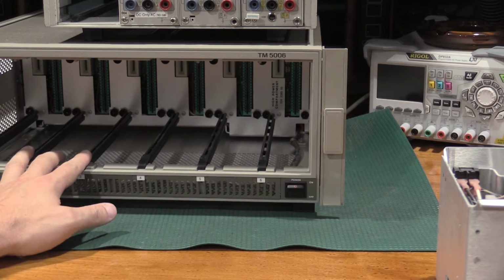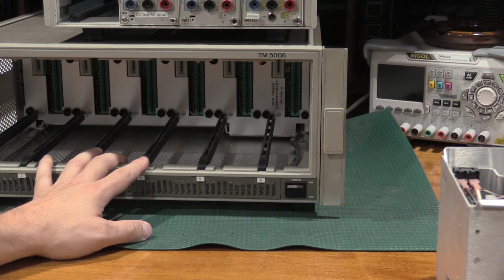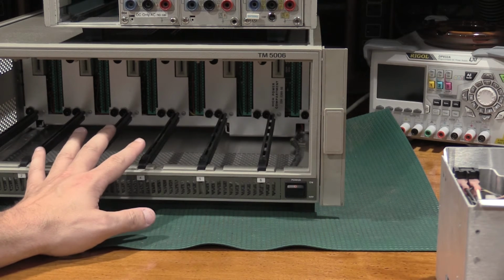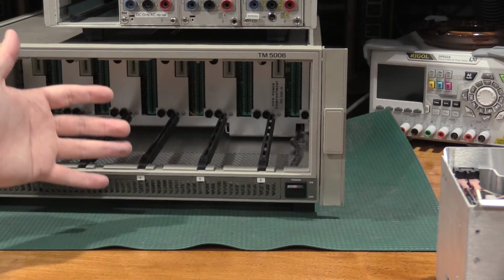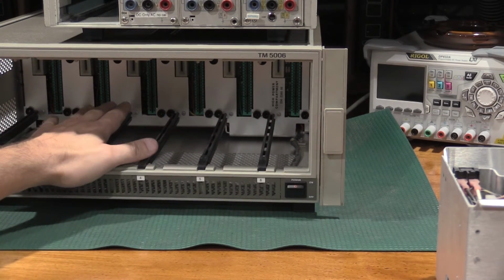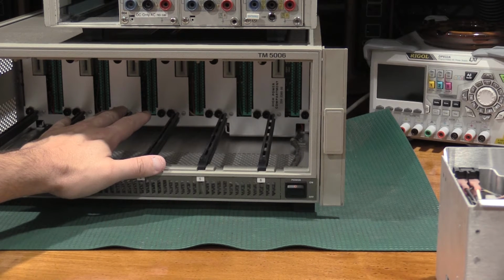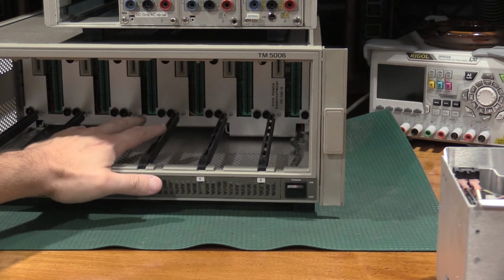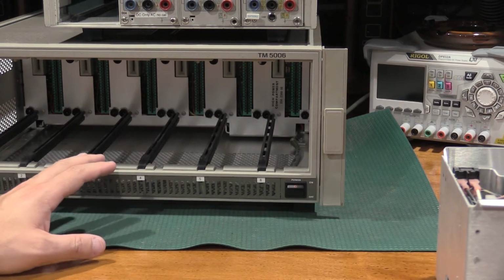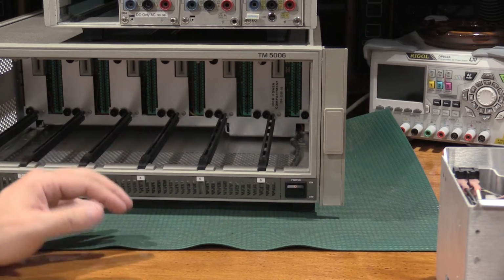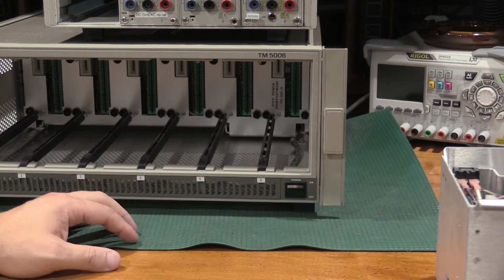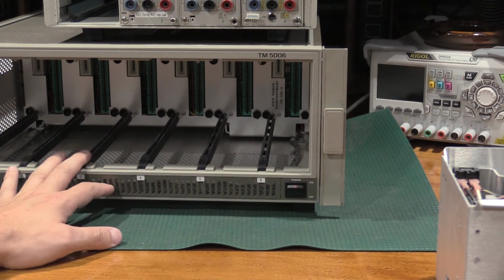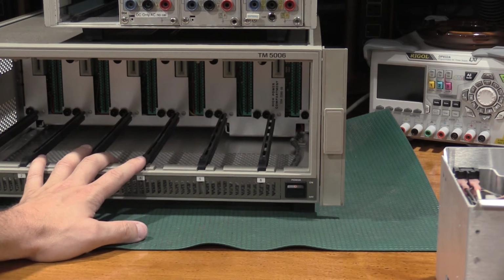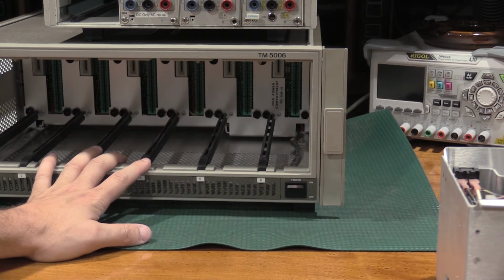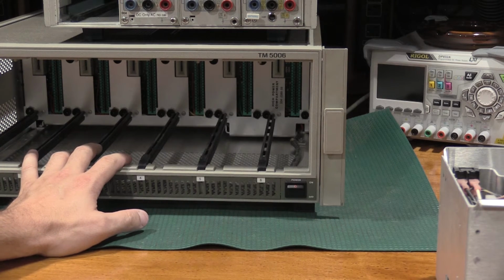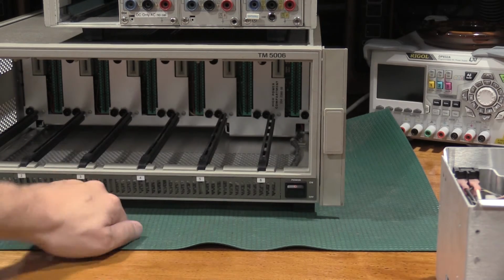The other thing is, this series from Tech was sold as complete modular test sets. So you get a bay, a couple of different instruments, and they would actually have interconnecting wiring on the back plane. That also meant the positions were locked. You couldn't just pop them out, move them around. All of my back planes, there's nothing there. But it is something you should check, especially if you're getting just a naked power frame without plug-ins, just check that there's nothing interconnecting any of the ports together, so that you don't feed signal where you're not expecting it and cause some damage to a plug-in.